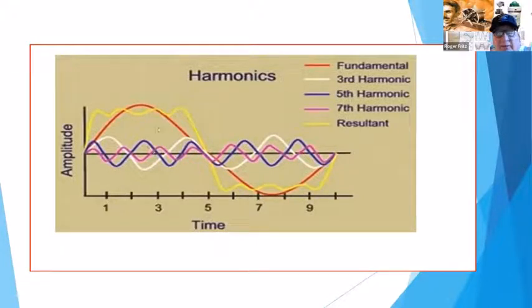So that's when they went back and said, okay, in order to adjust some of these, I went and put line reactors on the front. They put fifth harmonic traps, which are basically just a trap that was designed at 300 hertz that would suck off this power and drive it to ground. And so typically on a 6-pulse bridge, like it's done in most VFDs or DC machines, you'll see this harmonic content. But it's different in every circuit, and it's different dependent on your transformers, your wire size coming to where the drive is, everything, because you're creating a harmonic signal on those wires. It even creates issues about wire life.